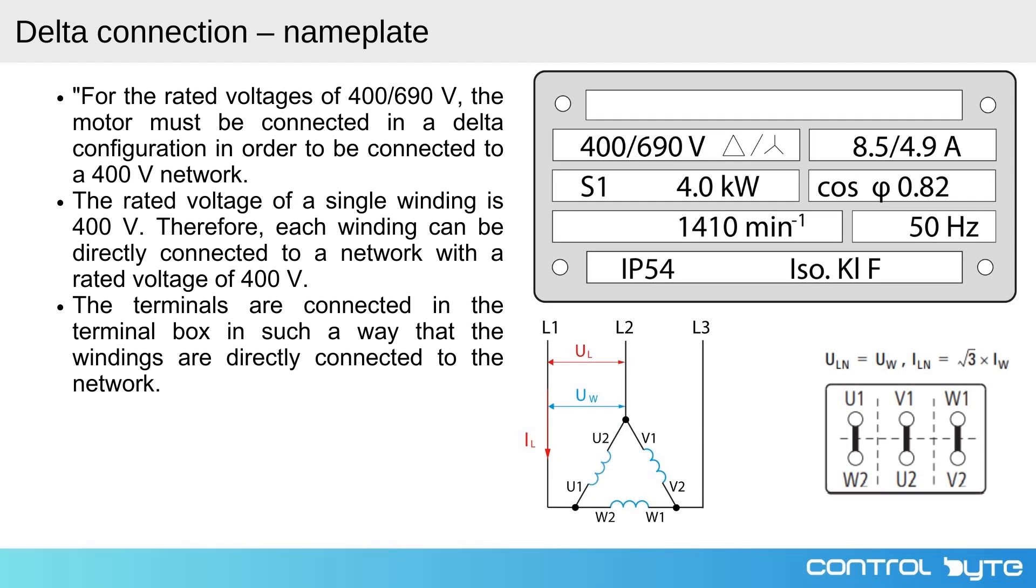In the previous slide we discussed the star connection. Now let's explore the delta connection and how it compares to the star configuration. Looking at this motor nameplate, we see the voltage ratings listed as 400/690 volts. This indicates that the motor must be connected in a delta configuration when operating on a 400 volt supply.